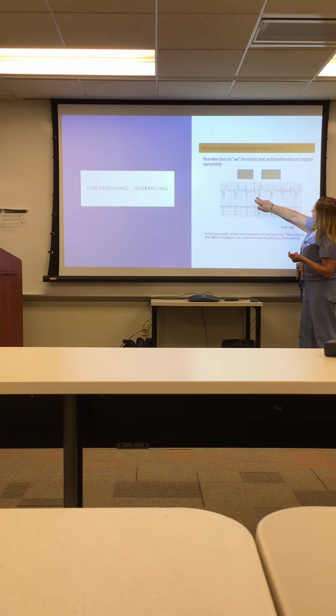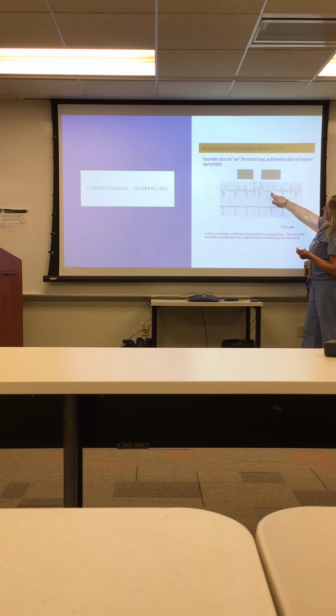You'll see another, this is an intrinsic that came through, but it's not sensed. This is actually a good captured beat there, and it's capturing, but the problem you'll get into, it starts acting in an asynchronous mode, so it's gonna deliver that paced beat inappropriately, and it could deliver it on an intrinsic T wave. So that's what you gotta be careful of when you look at that. So if you're like, okay, why, this is obviously not seeing anything, I need to adjust my sensitivity so it can see my R waves, and we're not pacing on T, okay?